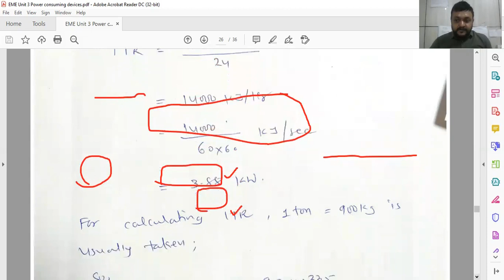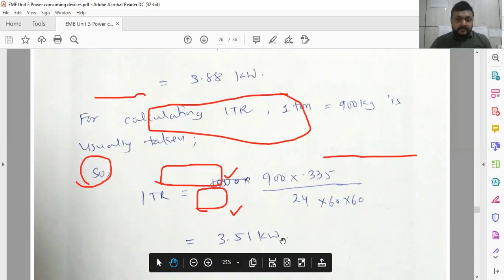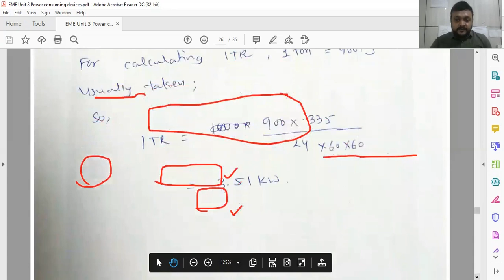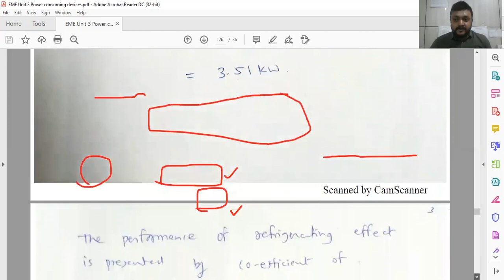1 ton is ideally taken as roughly 1000 kg, but the actual amount is not 1000. So nearly we have to take it as 900 kilogram instead of 1000 kilogram. So 900 kilogram into 335 divided by 24 multiplied by 60 multiplied by 60 gives 3.51 or 3.88, which is more or less similar. So roundabout, you have to keep in mind that about 3.5 to 4 kilowatt is the 1 ton of refrigeration.